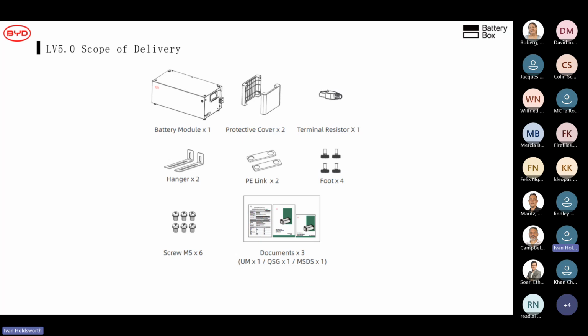What you do get in the box is 1 battery and 2 covers. Those go on either end, and a termination resistor. It's very important when you're putting batteries in parallel to insert the termination resistor. They won't work if the termination resistors aren't inserted. And then there are 4 feet in each battery. They are a floor mount battery, so it's not recommended that you install them on walls.